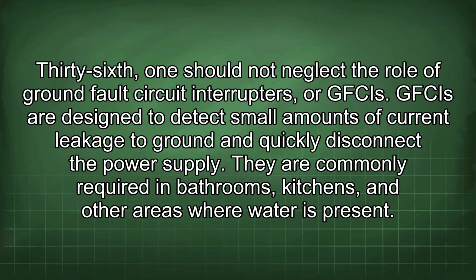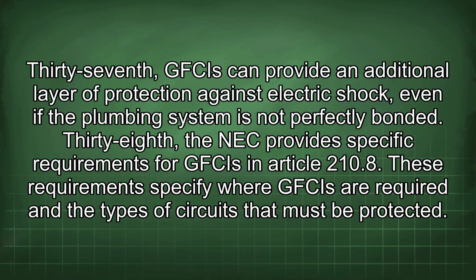36th, one should not neglect the role of ground fault circuit interrupters, or GFCIs. GFCIs are designed to detect small amounts of current leakage to ground and quickly disconnect the power supply. They are commonly required in bathrooms, kitchens, and other areas where water is present. 37th, GFCIs can provide an additional layer of protection against electric shock, even if the plumbing system is not perfectly bonded. 38th, the NEC provides specific requirements for GFCIs in Article 210.8. These requirements specify where GFCIs are required and the types of circuits that must be protected.